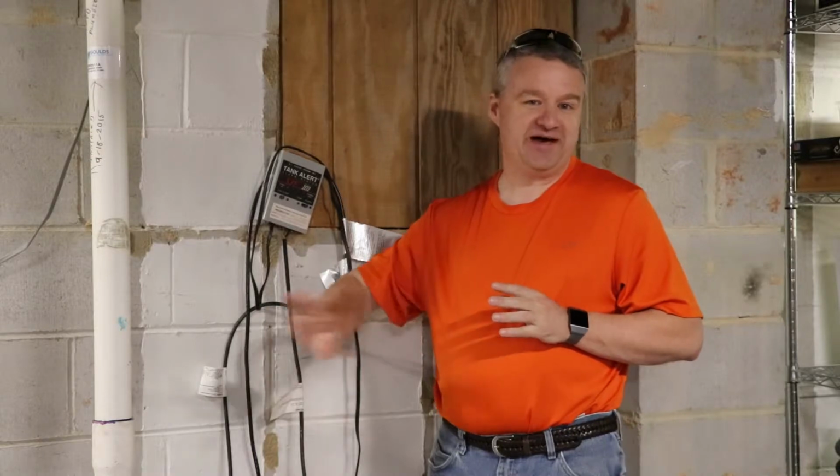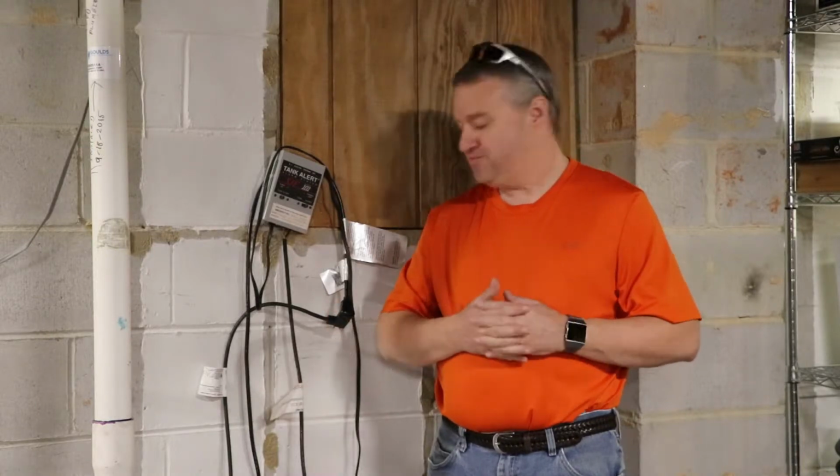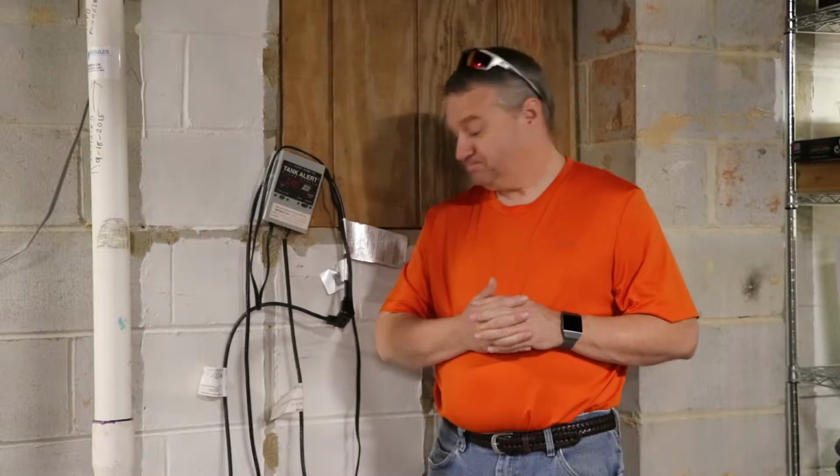One of the reasons this project has been pushed back and back and back is because with a basement sump pump, you basically have a reservoir under the concrete with a pump and pipe coming out. The one that was here has four bolts holding it all together. The bottoms of the bolts are down to the concrete. You can't get to them the way that this one was put in. And they pretty much were all rusted shut. So getting this apart was not going to be fun.